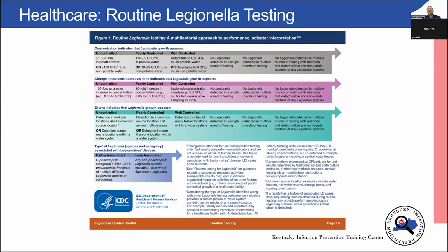In this top bar here is the gray line. That's for potable water, the top half of that Legionella routine testing analysis. And what it's telling you is if it's above 10 CFU at any location, and the CDC uses basically zero tolerance, they're not concerned about how many samples you've taken and what your percent positive is. They're concerned about each individual site: is it controlled or uncontrolled? Above 10 CFUs per mL in your Legionella samples, you're definitely uncontrolled, and that's going to cause you to take an instant response.